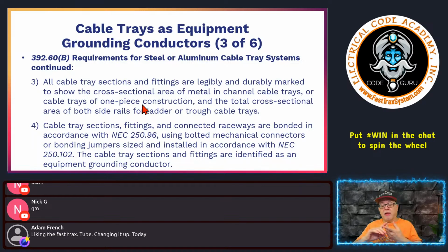When the electrician looked at it, they didn't put equipment grounds in there, thinking the engineer knew what he was talking about, but they didn't read the notes that the cable tray system had to be marked and have all of this stuff on it to be used as an equipment grounding conductor. But it didn't have any of that. So there was a communication mix-up between the engineer, which really wasn't the engineer's fault because he said what to do, and the contractor and whoever procured it. They didn't pay attention to those details. It was a messy thing, and it really sucks because they were right at the end of a project. That can cause a crappy day. I'm just saying.